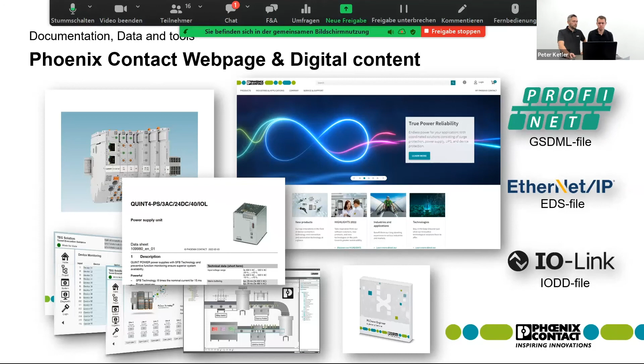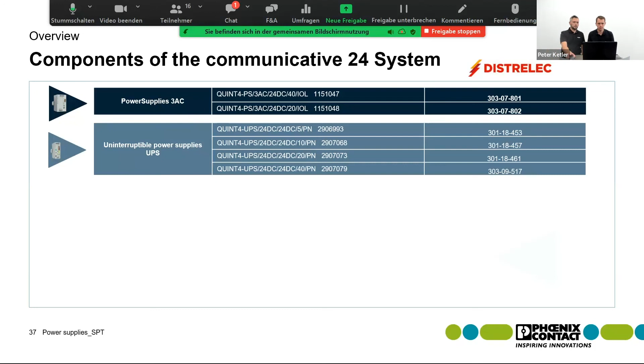Now, where can you order the components of the communicative 24-volt system? To separate the different types of components, we start with the power supply - two versions in three-phase, 24-volt DC, 40 amp and 20 amp IO-Link. You can order them on the Distrelec webpage under these article numbers. Next is the Quint DC UPS, available in the Profinet variant in 5, 10, 20, and 40 amp versions, 24 volts DC - this is a selection of our portfolio. We also have the same power classes in other field buses, such as Ethernet IP, EtherCAT, and Modbus.